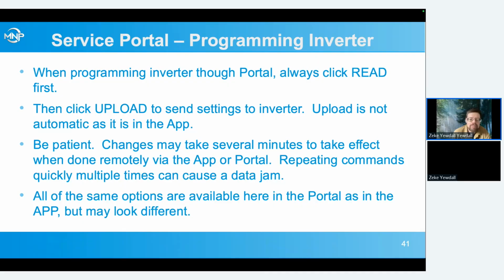When you're programming the inverter remotely, especially, you need to be patient. Sometimes it can take several minutes for these changes to take effect. And if you keep hitting it, it can cause a data jam, and then the whole inverter will lock up sometimes for quite a while, like half an hour. So just be patient and give it 5 or 10 minutes to change what it's doing after you've changed the settings. It's not instantaneous all the time.